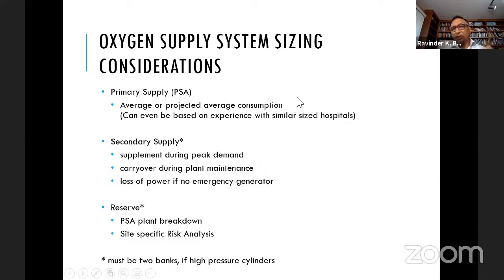So it's recommended that sizing be based on average consumption, or your projected average consumption in future. You can also use similar experience from other hospitals, there are many hospitals in the world using these systems, so there's a lot of experience and papers available that people can read. The secondary supply could be a liquid oxygen tank or high pressure cylinders, and that's meant to supplement oxygen during peak load.